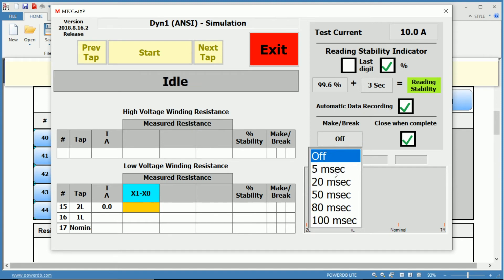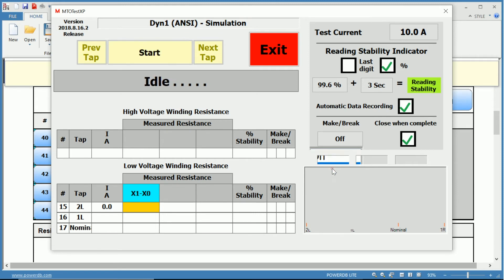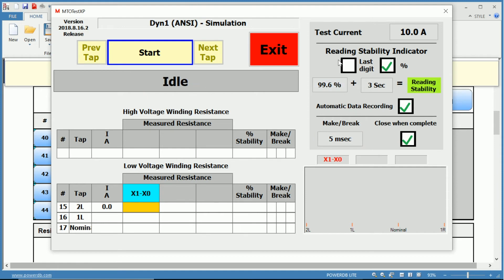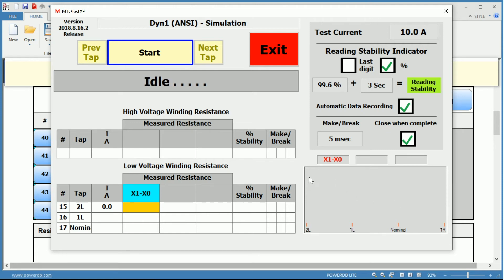For your make-before-break, depending on the manufacturer specifications, this can range anywhere from five milliseconds to one hundred milliseconds. And you have the option to close this once it's complete. So once we've gone through and we've selected all of our tests, we can go through and start the test.